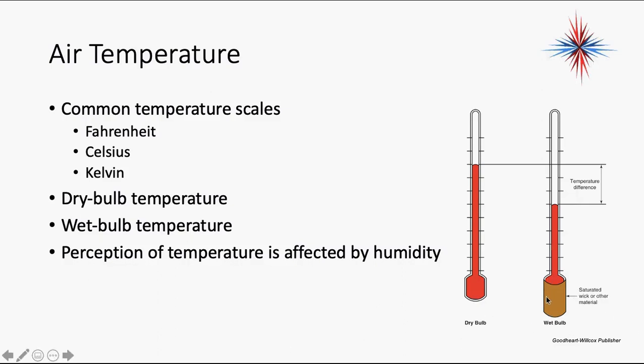One of the things we used to use before all these electronic tools, to do wet bulb and dry bulb temperatures, was our meter leads with old shoelaces. Cut a piece off an old cotton shoelace, put it over the end, hold it on there, and wet it down. Cotton shoelaces are a great wick for wet bulb temperature. I still know a lot of technicians who prefer this approach over any electronic tool. With most electronic tools, as the batteries get weaker, the tool won't give you the right reading. You'll find that on your meters too eventually, as batteries wear out, readings change. As soon as you see a low battery light, the readings change.